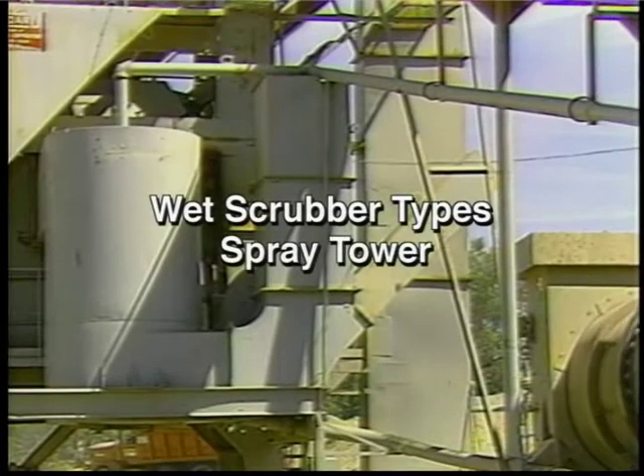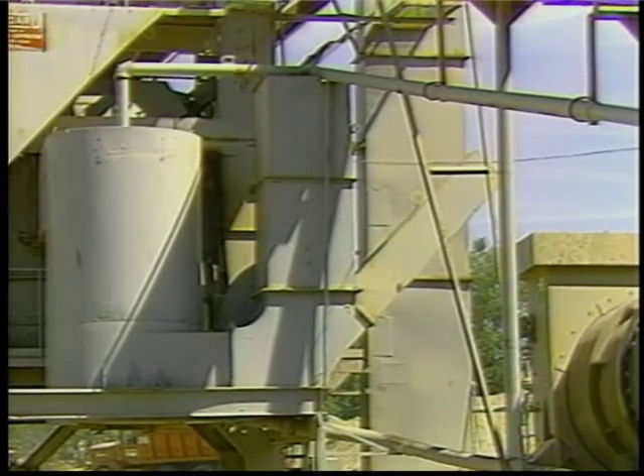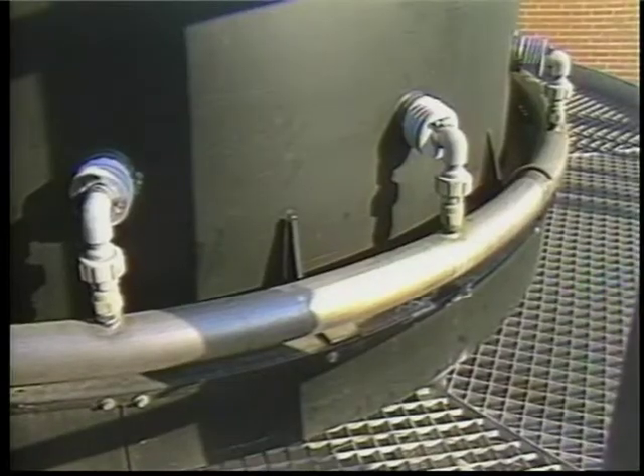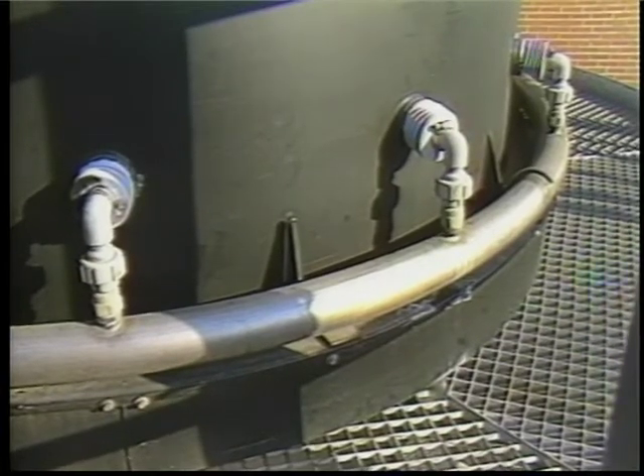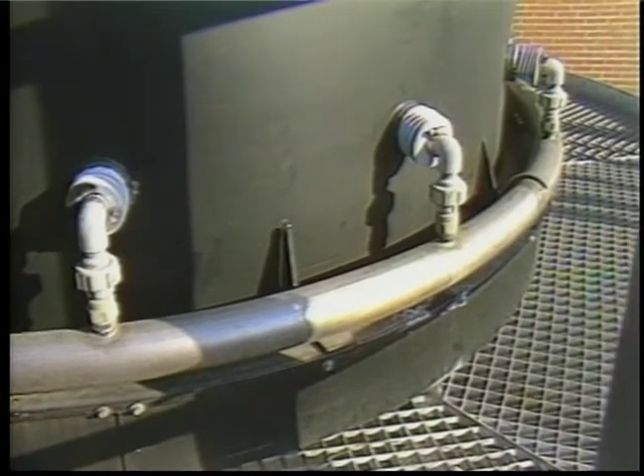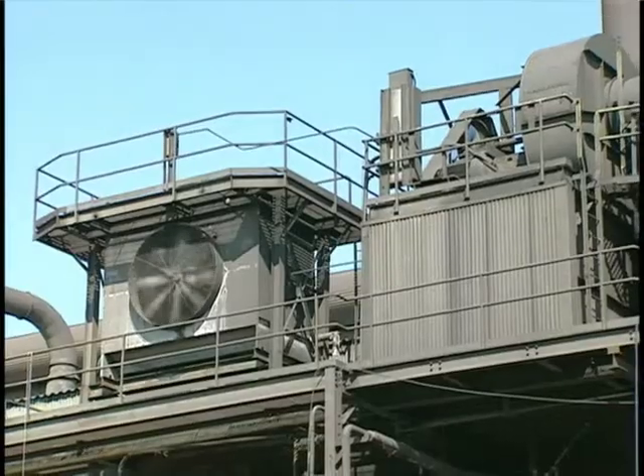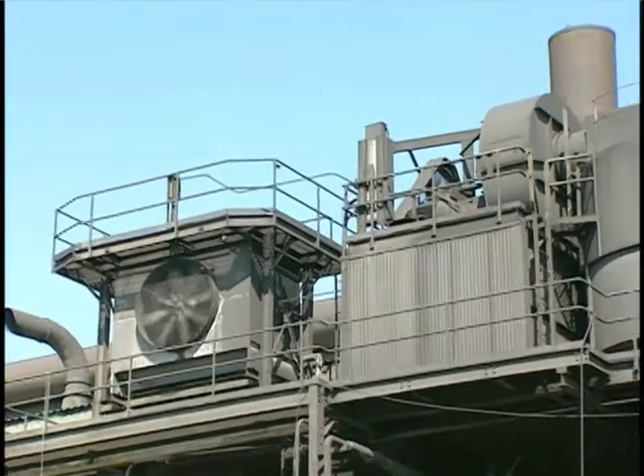The spray tower is a low energy device and is the simplest wet scrubber used for particle collection. It consists of an open vessel with one or more sets of spray nozzles to distribute the scrubbing liquid. Typically the gas stream enters at the bottom and passes upward through the sprays. The particles are collected when they impact the droplets.